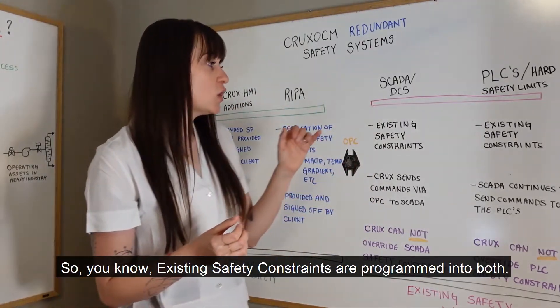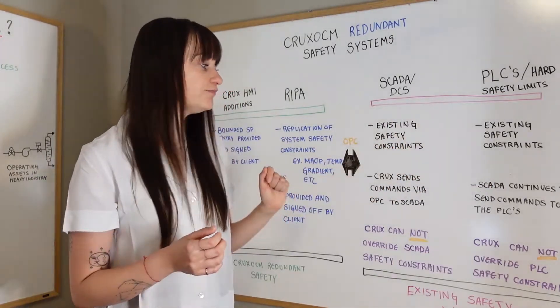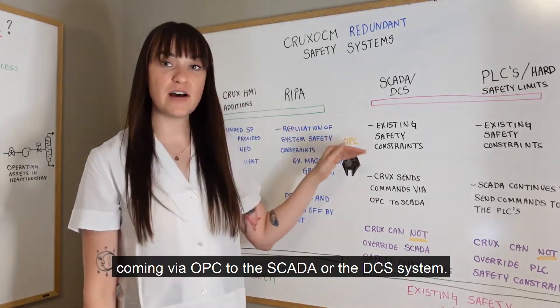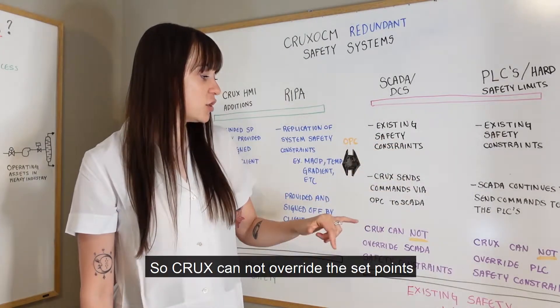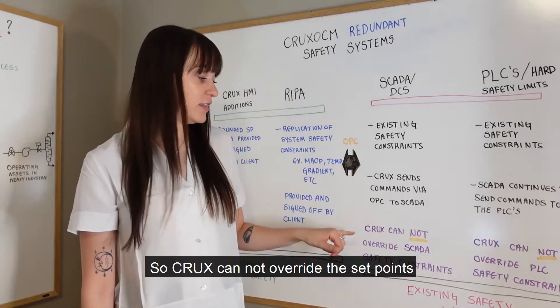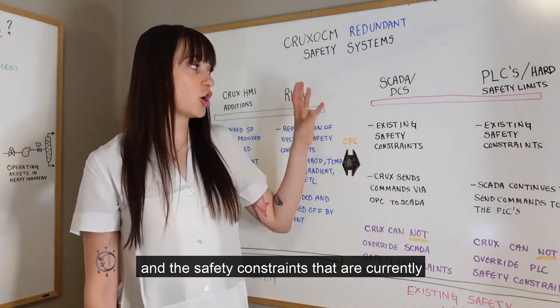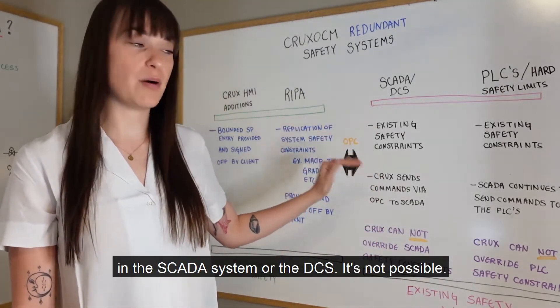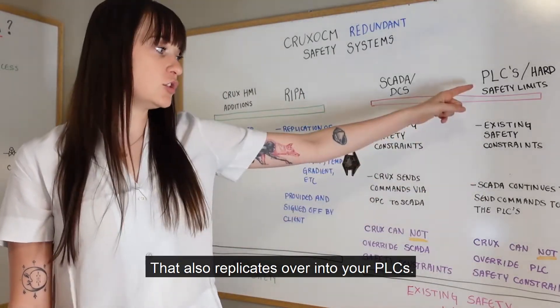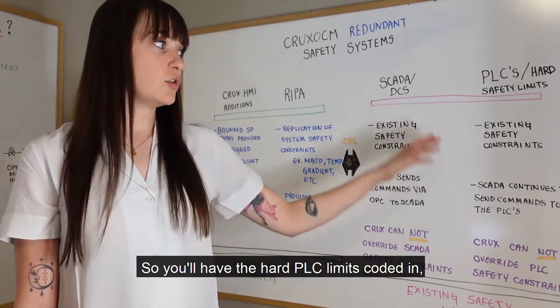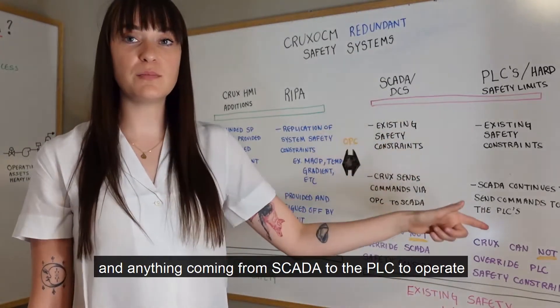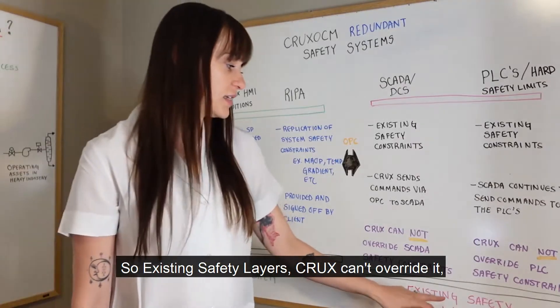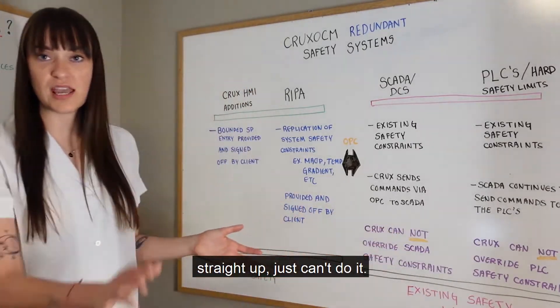Existing safety constraints are programmed into both systems. When Crux OCM's RIPA software sends set points via OPC to the SCADA or DCS system, Crux cannot override the safety-constrained set points currently in the SCADA or DCS — it's not possible. That also replicates into your PLCs, where hard PLC limits are coded in and anything coming from SCADA to the PLC cannot override those constraints. Crux simply can't override existing safety layers.